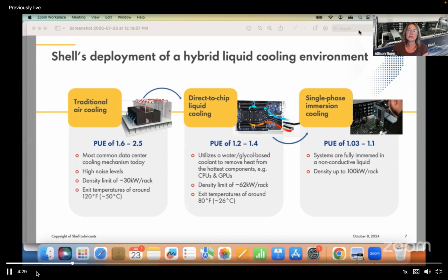That's with one of our trusted partners, GRC, Green Revolution Cooling. Now that's running in full production at 100 kW per rack, which equates to 2 megawatts of the overall 7 megawatts they're doing. It's fun to hear some of the numbers—they're running 9 petaflops in the tanks on site, and the data hall itself is only around 20 petaflops. So literally they're running half of their production environment in single-phase immersion cooling fluid, and it's really exciting to see. I know you got to witness that.